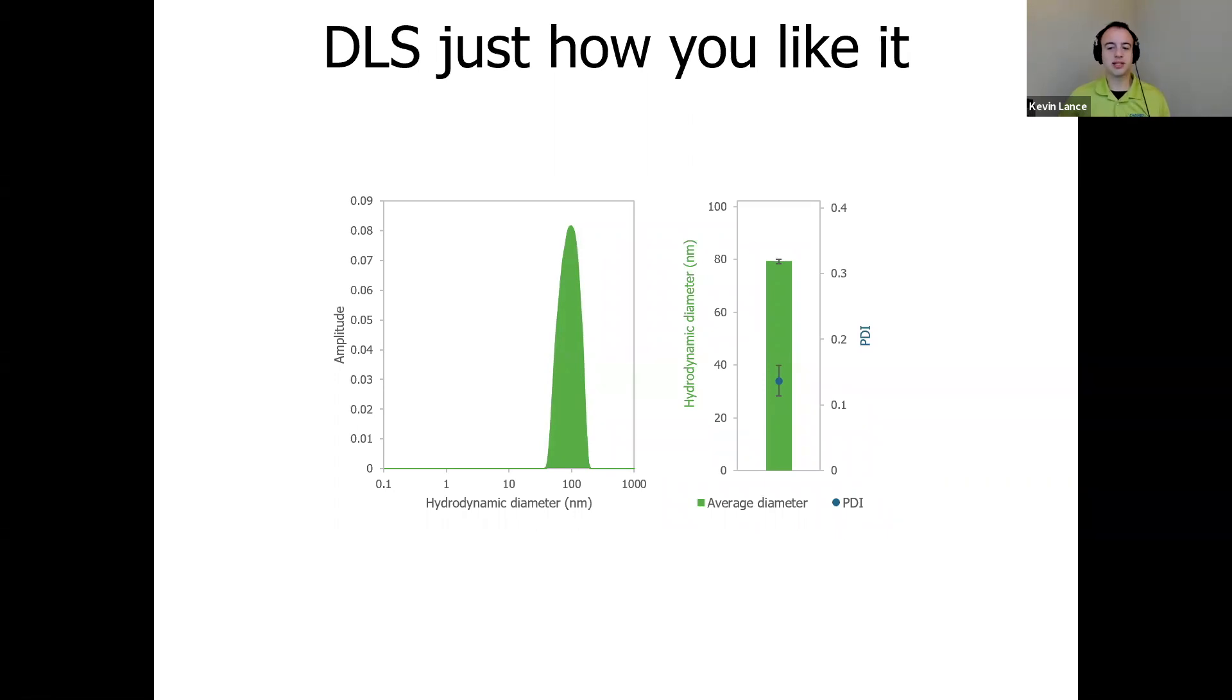So all this DLS data is just how you like it, delivering up quick intensity and mass distributions, hydrodynamic diameter and PDI values, but now you can add the throughput that lets you get a really great understanding of the precision you have in your sample. So you don't need to stick to an n of one for your DLS data anymore. You can actually run triplicates, quadruplicates, duplicates, you name it.